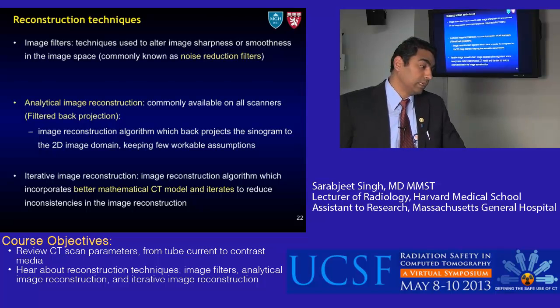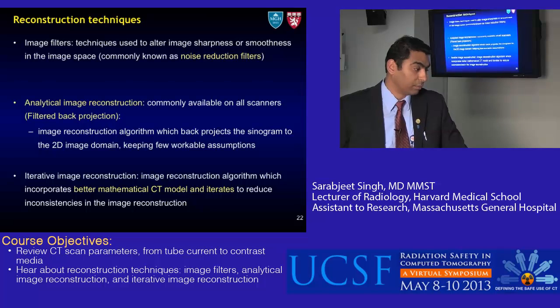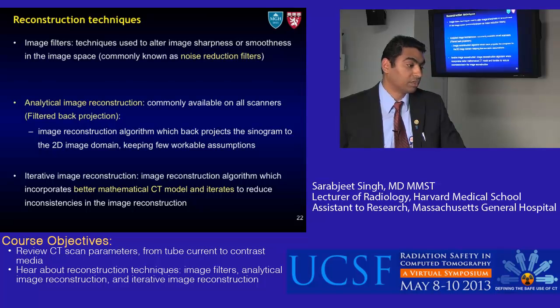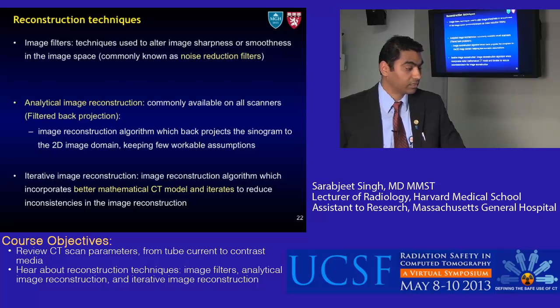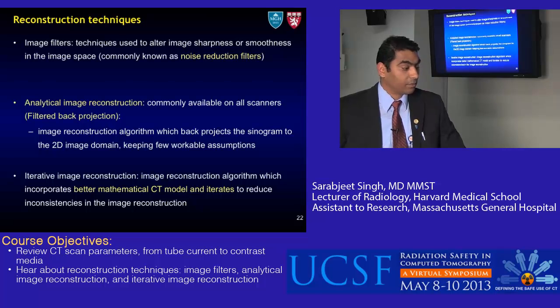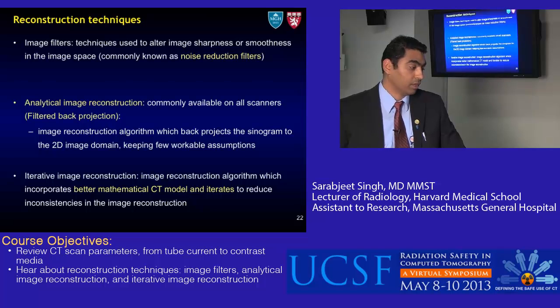Next, reconstruction techniques. Several new techniques are coming to market, so it's important to understand their definitions. Image filters are techniques used to alter image sharpness or smoothness in the image space, commonly known as noise reduction filters. Analytical image reconstruction — filtered back projection (FBP) — is the standard technique available on all scanners. FBP is an image reconstruction algorithm that back-projects the sinogram to the 2D image domain using workable mathematical assumptions. It's a fast technique that has served well for the past 40 years.